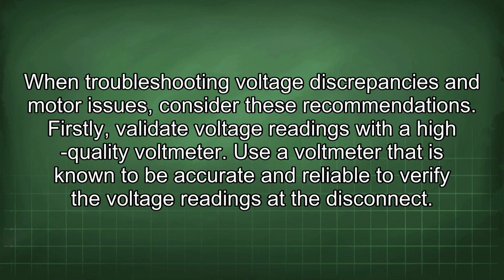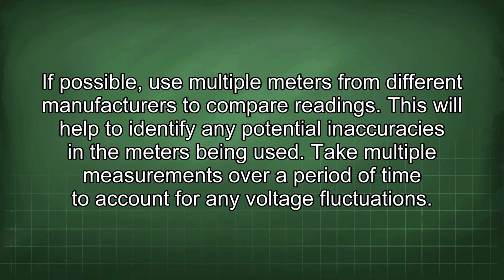When troubleshooting voltage discrepancies and motor issues, consider these recommendations. Firstly, validate voltage readings with a high-quality voltmeter. Use a voltmeter that is known to be accurate and reliable to verify the voltage readings at the disconnect. If possible, use multiple meters from different manufacturers to compare readings. This will help to identify any potential inaccuracies in the meters being used. Take multiple measurements over a period of time to account for any voltage fluctuations.